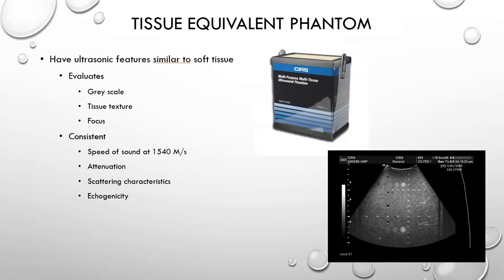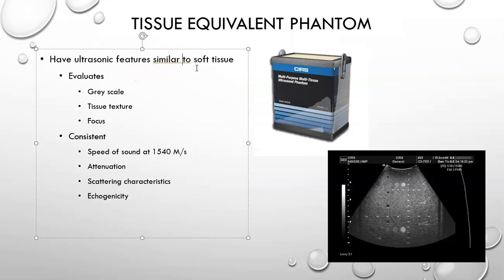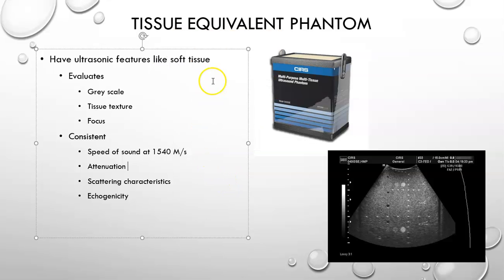So to do that, we use a tissue equivalent phantom, which will have features very similar to soft tissue. Wonder why that is. Okay, we'll put in features like soft tissue. This helps us evaluate the grayscale, gives us a tissue texture, a focus, and it gives us a consistent speed of sound at 1540 meters per second.